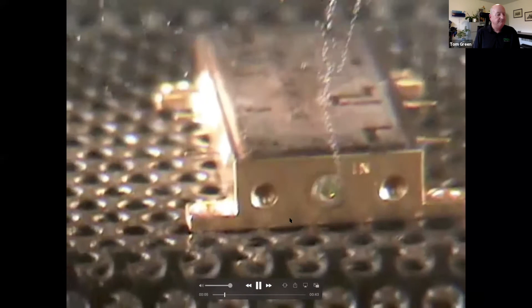So this is the bubble test. Right here, you can see a leaker. A lot of times there are a lot more feed-throughs, but this is a microwave feed-through, and gold embrittlement cracked it. That's on top of the port for the leak detector. We're dabbing some IPA, and you can see the bubbles indicating exactly where the leak path is.